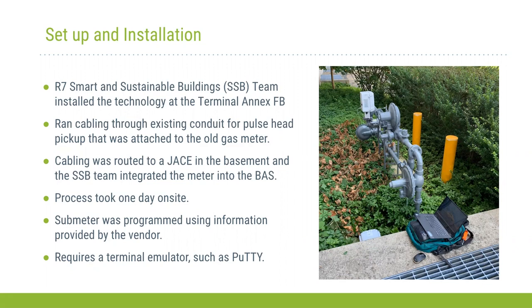The programming took him approximately an hour. He worked with the vendor, who had really great instructions for how to program the Modbus registers we needed. Region 7 has the benefit of our whole region being set up on a Tridium Niagara front end, so he built into the wire sheet a way for us to adjust the K factor remotely. When doing any of the programming directly on the vendor's device, it requires a terminal emulator for initial setup.